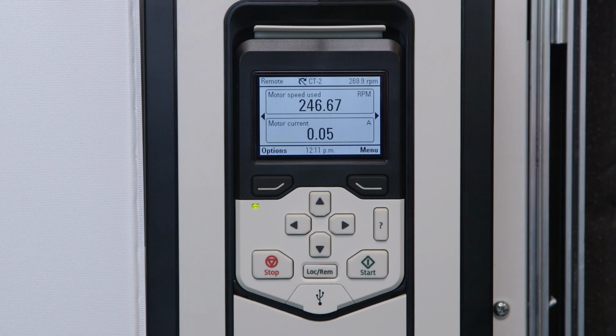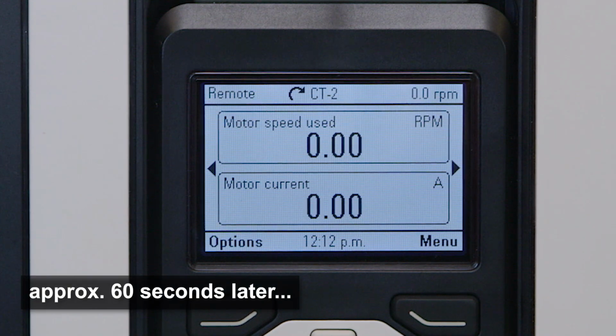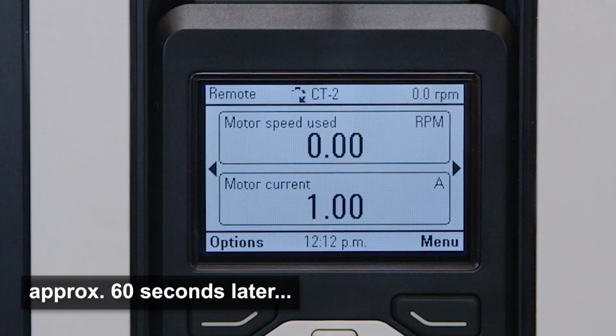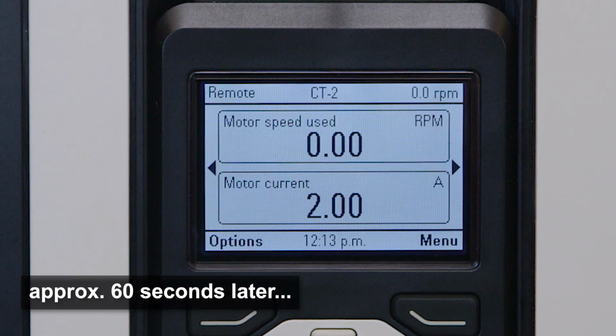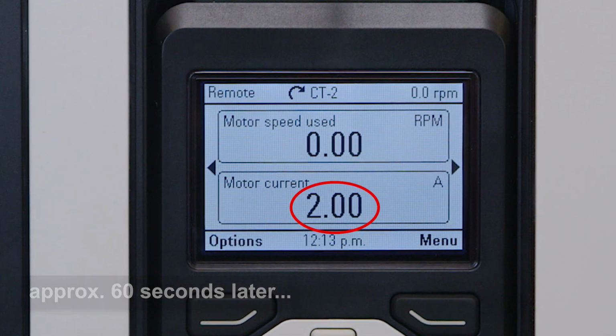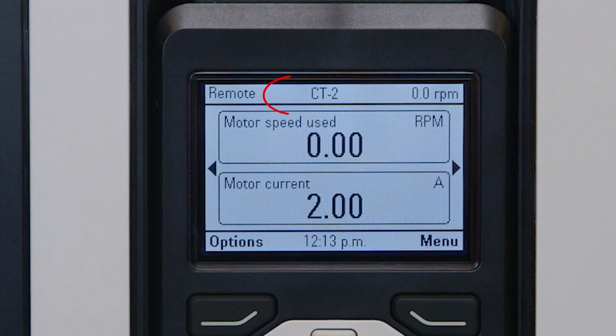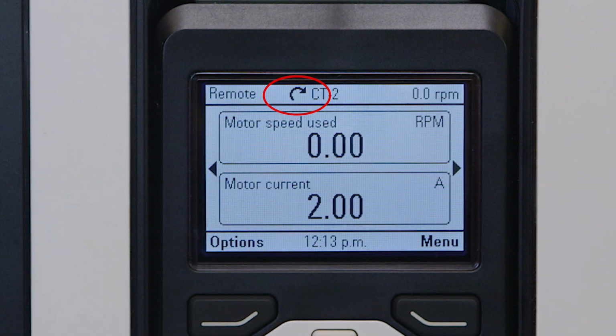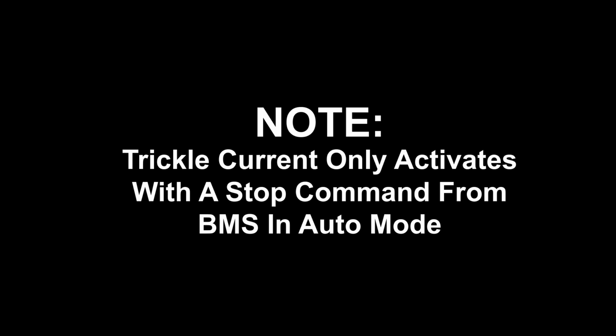Now, let's test the trickle current. Have the BMS send a stop signal and confirm the fan stops. Now ensure the trickle current activates. To do this, first wait for the trickle current delay to end. Then record the amps on the display. Confirm that the direction arrow is not rotating and that it is flashing. The trickle current only activates with a remote stop command. Trickle current will not activate in local mode. Also, trickle current will not activate if VFD is stopped in local mode, then changed to auto mode.